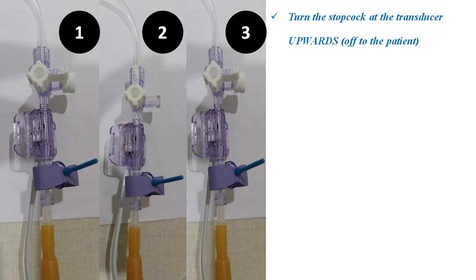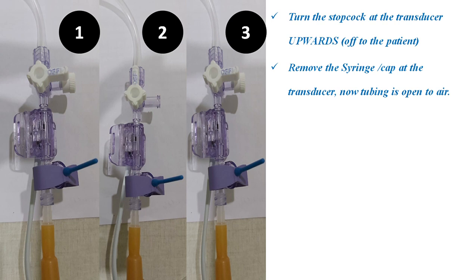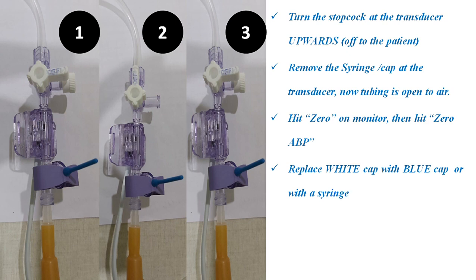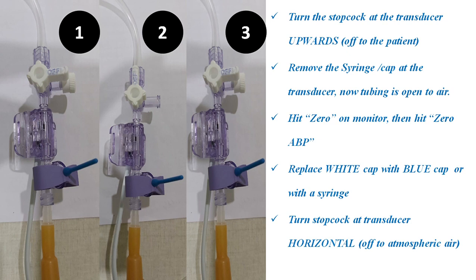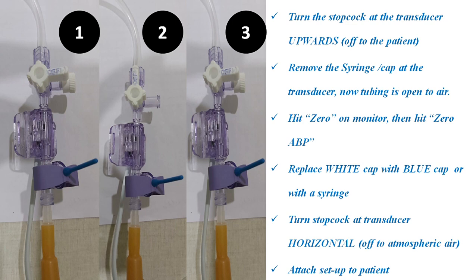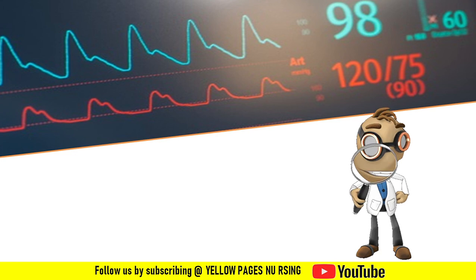Turn the stopcock at the transducer upwards, off to the patient side. Remove the syringe or cap at the transducer so the tubing is open to air. Hit 'zero' on the monitor, then hit 'zero ABP.' Replace the white cap with a blue cap or syringe, then turn the stopcock at the transducer horizontal — off to atmospheric air. Now attach the setup to the patient's arterial line. Once attached, a clear waveform will appear on the monitor.